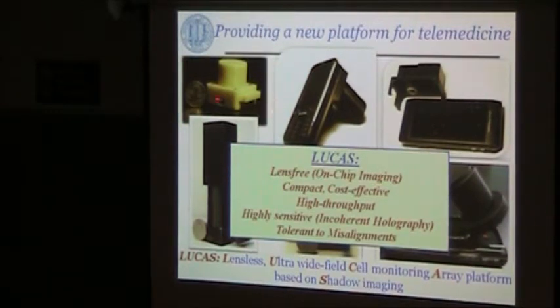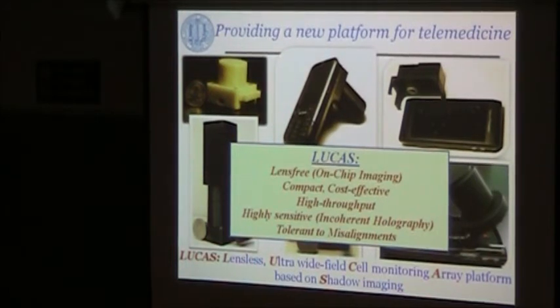Even this small microscope here can deliver more than a 20 millimeter square field of view with around 0.1 to 0.2 numerical aperture, which is quite large compared to a conventional microscope, as I'll be showing you, which typically looks at sub-millimeter square regions.